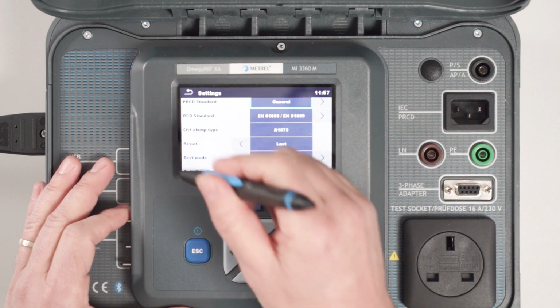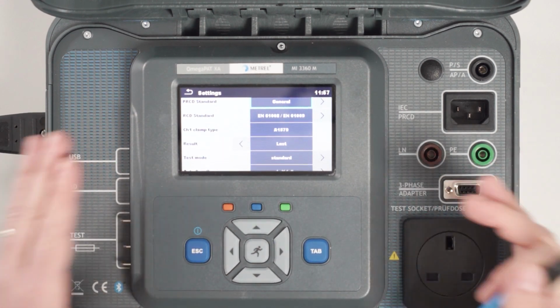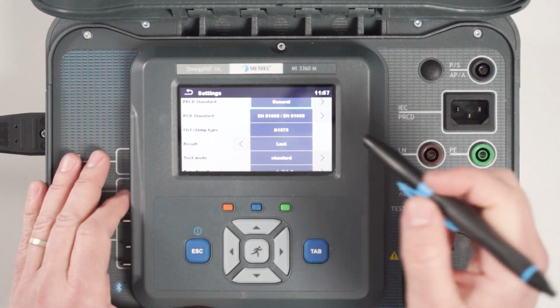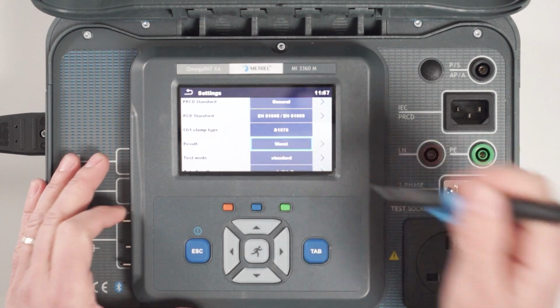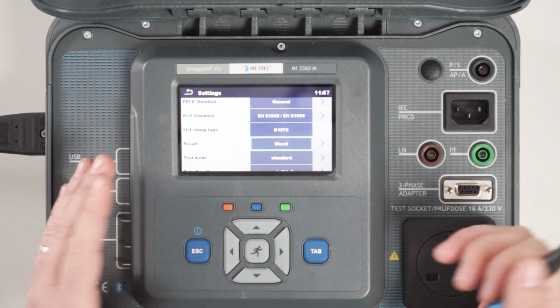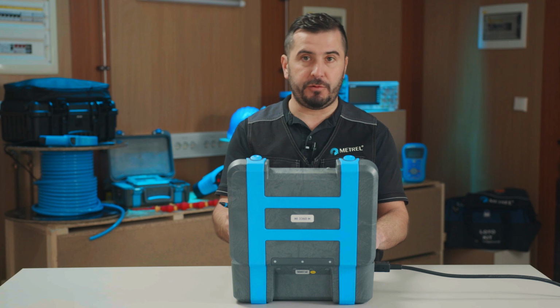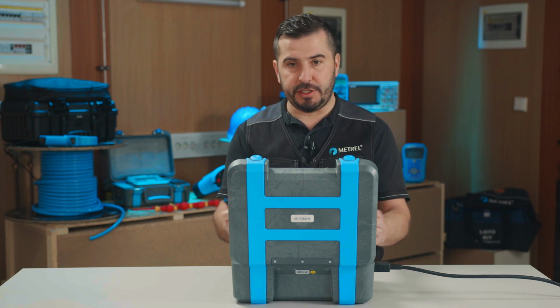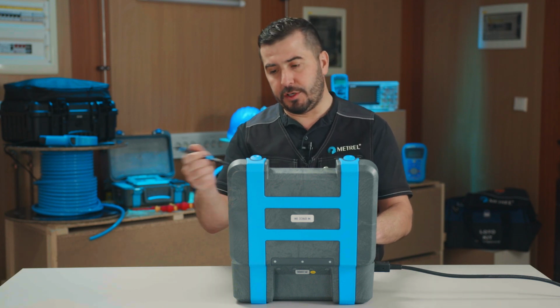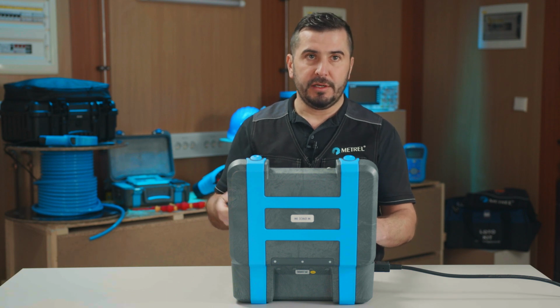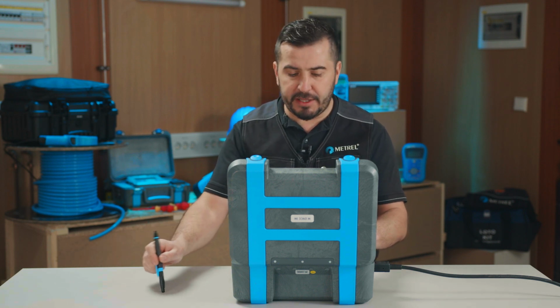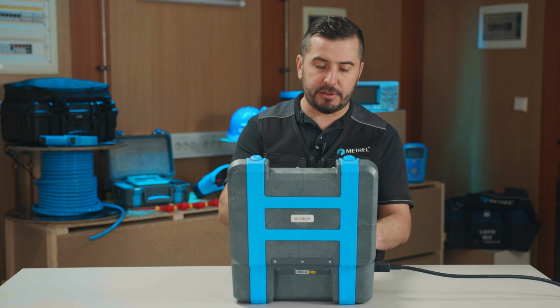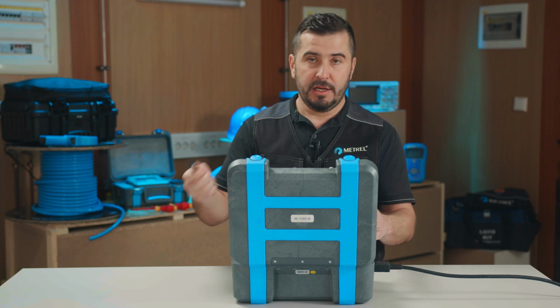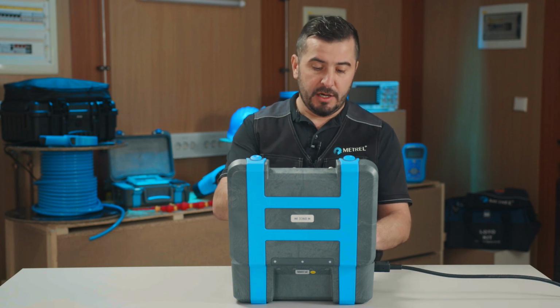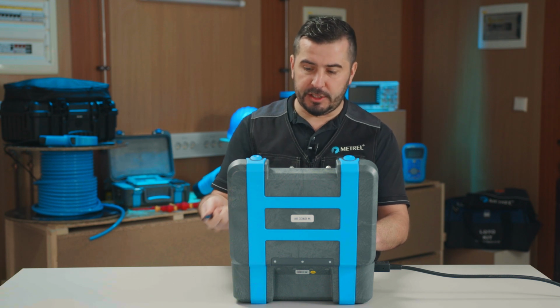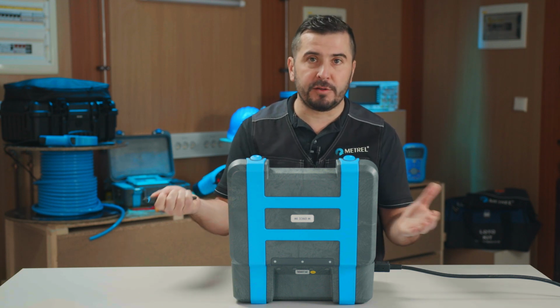By default, the results we obtain from the measuring sequence are set to last, but we can change this also to worst. A short explanation maybe. So for example, if we are measuring earth continuity on multiple points, starting maybe with a bad contact, it is maybe better to set to last. So we will actually see on the screen the last result that was when we had good contact.